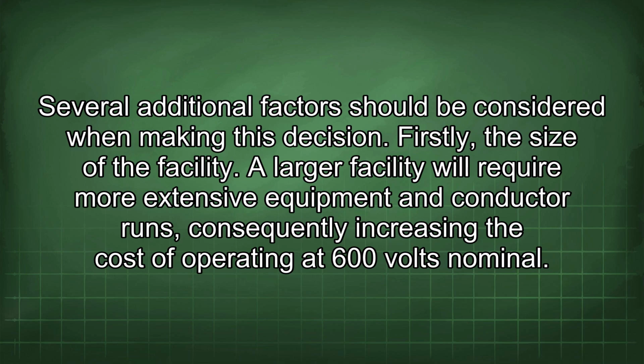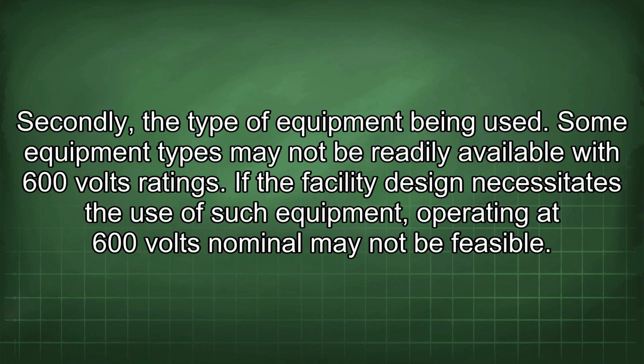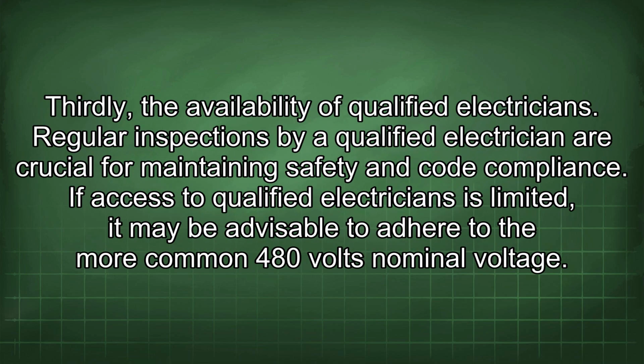A larger facility will require more extensive equipment and conductor runs, consequently increasing the cost of operating at 600 volts nominal. Secondly, the type of equipment being used. Some equipment types may not be readily available with 600 volts ratings. If the facility design necessitates the use of such equipment, operating at 600 volts nominal may not be feasible. Thirdly, the availability of qualified electricians. Regular inspections by a qualified electrician are crucial for maintaining safety and code compliance.